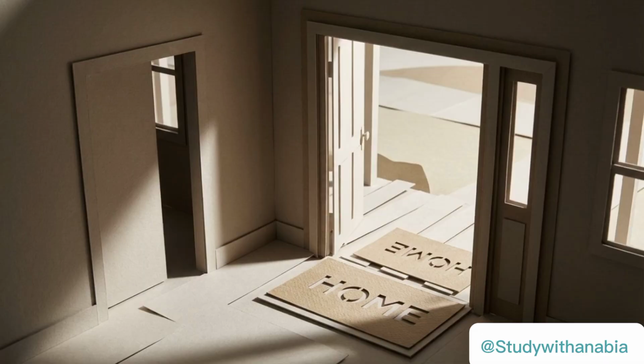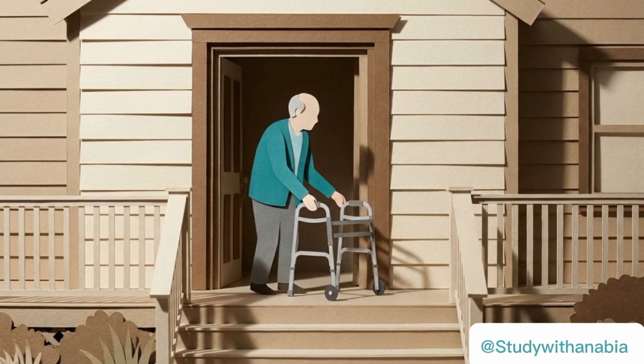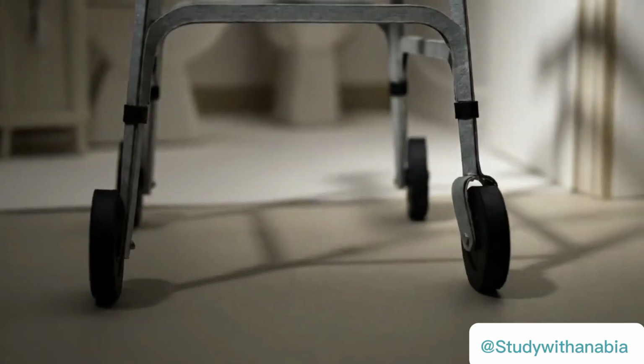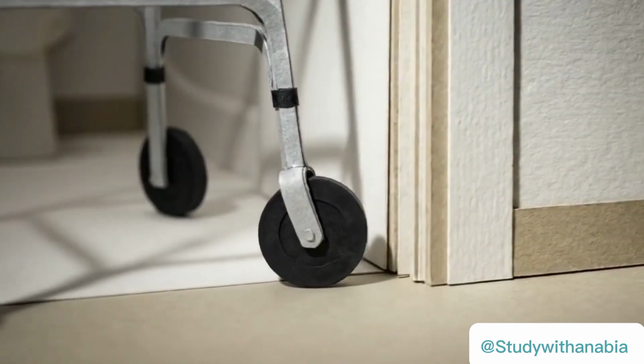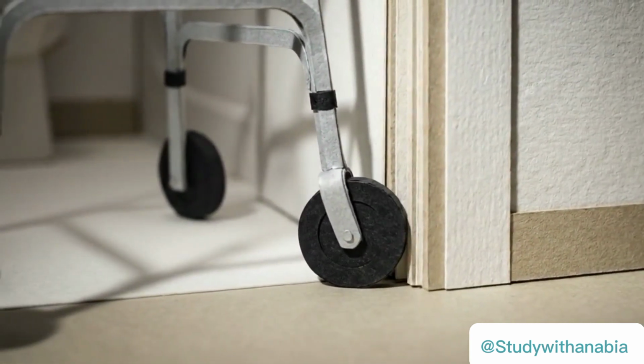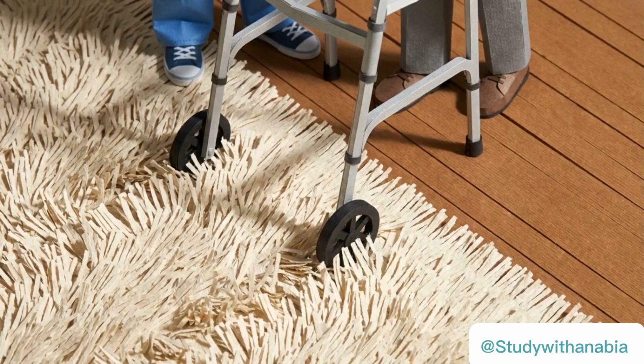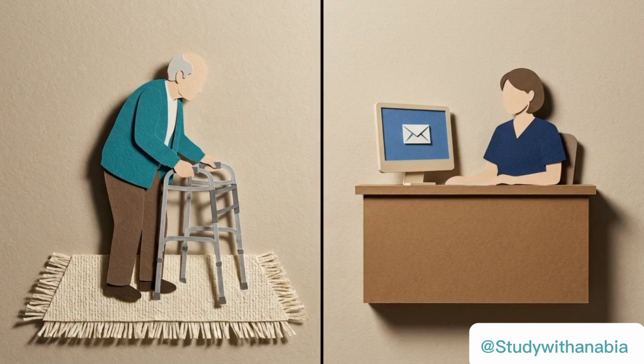To see if the tool truly works, we move to step 3, comparison field testing. The patient takes the device home and uses it in their actual environment for several days. The real world introduces variables a sterile clinic simply cannot replicate. The walker has to navigate tight bathroom hallways, transition from hardwood to thick rugs, and support the patient while they do actual household chores. If the device fails out there, the therapist enters the loop.